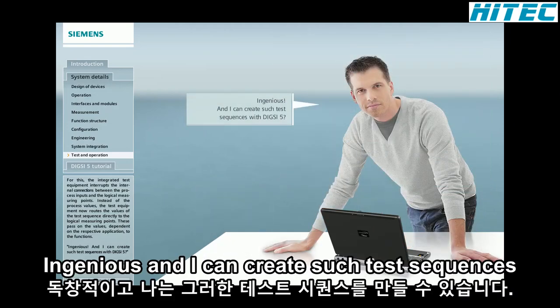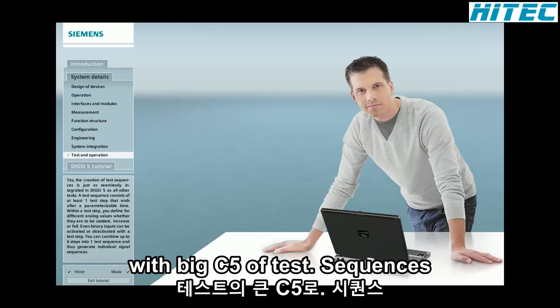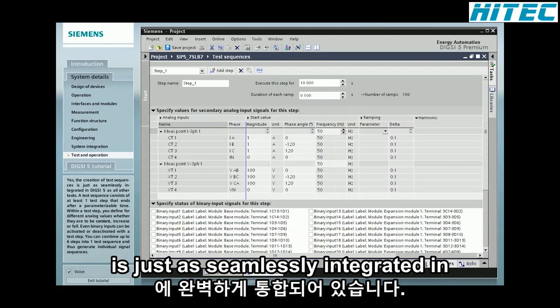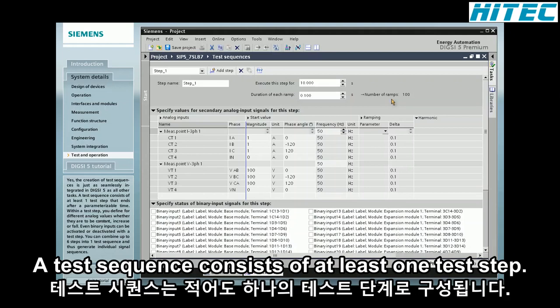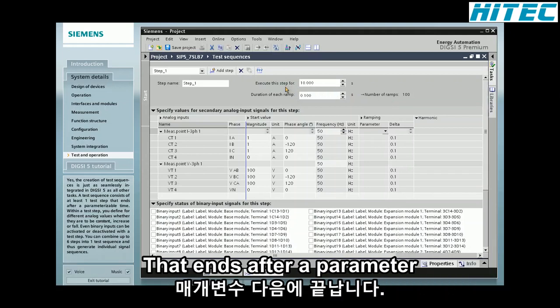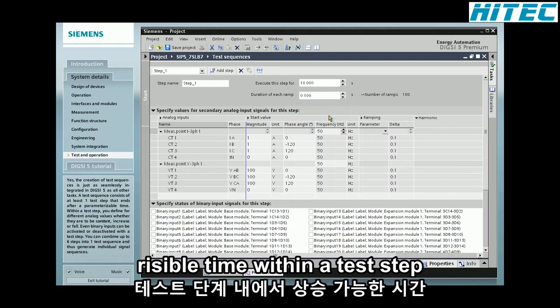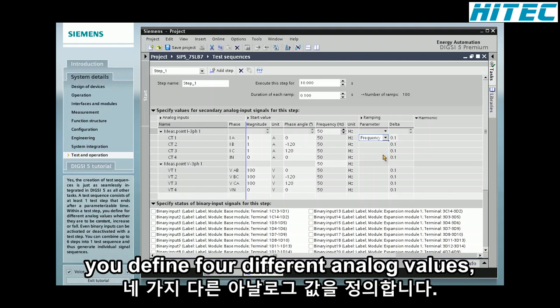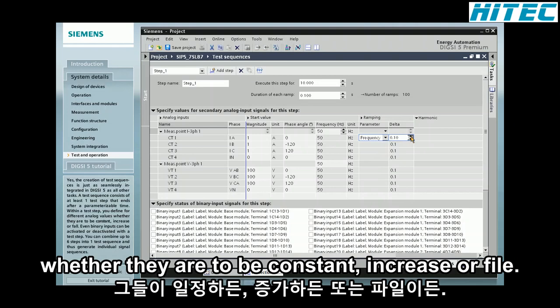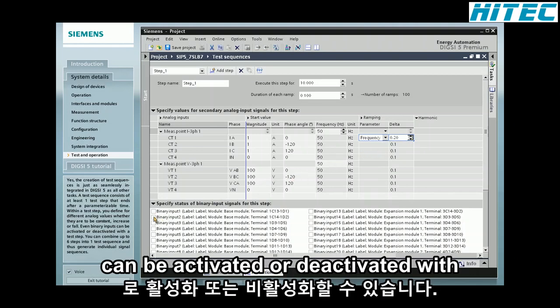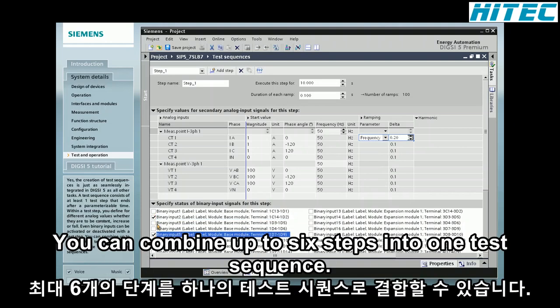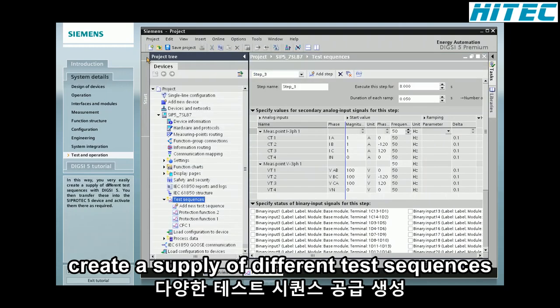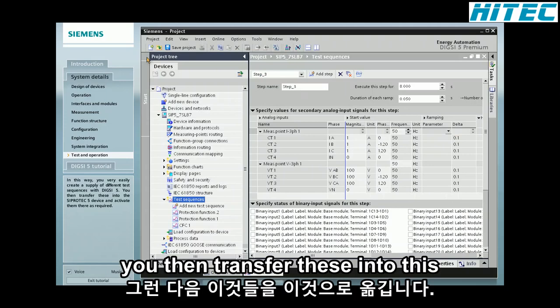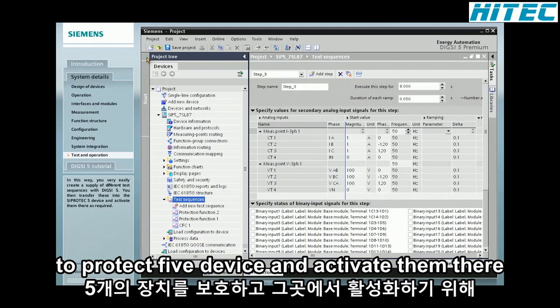Ingenious! And I can create such test sequences with DIGSI 5? Yes, the creation of test sequences is just as seamlessly integrated in DIGSI 5 as all other tasks. A test sequence consists of at least one test step that ends after a parameterizable time. Within a test step, you define for different analog values whether they are to be constant, increase, or fall. Even binary inputs can be activated or deactivated with a test step. You can combine up to 6 steps into one test sequence and thus generate individual signal sequences. In this way, you very easily create a supply of different test sequences with DIGSI 5. You then transfer these into the SIPROTEC 5 device and activate them there as required.